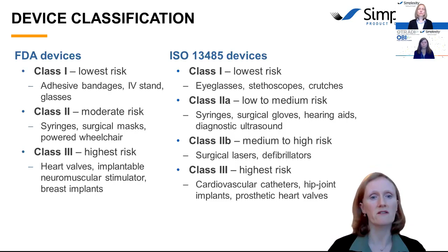But once you have classified your device, software is actually classified separately. And this is the classification that drives the level of rigor needed in software. In the FDA, they call these levels of concern. Minor level of concern is where a failure in software is unlikely to cause injury to a patient or operator. Moderate is where failures could directly result in a minor injury. And major is where death or serious injury could happen.